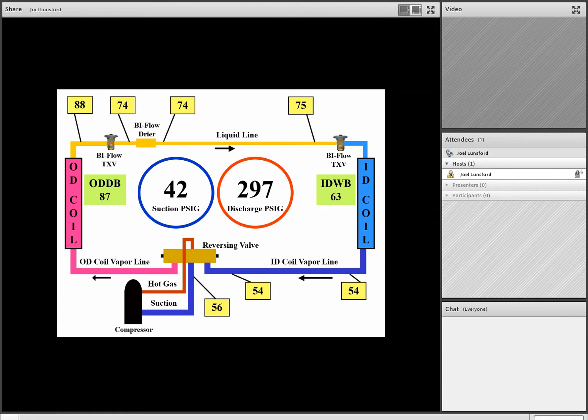Now, as we take a look at this refrigerant screen, we see our suction pressure is actually lower than we'd expect on an R22 call in the cooling mode of operation. We also notice that our discharge pressure is somewhat elevated. Well, if we take the superheat on the indoor coil, which is cold, we see at 42 pounds of suction pressure for R22, we're running approximately 19 degrees of pressure temperature conversion at 42 pounds of pressure. However, 19 degrees compared to a 54 degree indoor coil vapor suction line temperature, we see that we have over 30 degrees of superheat. So the indoor coil in this example is starved.